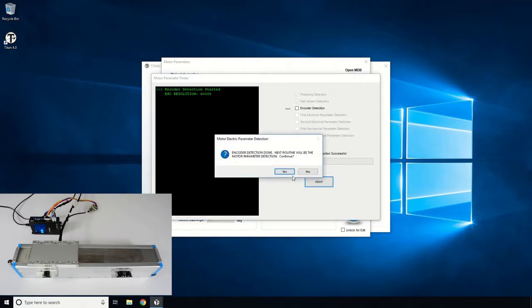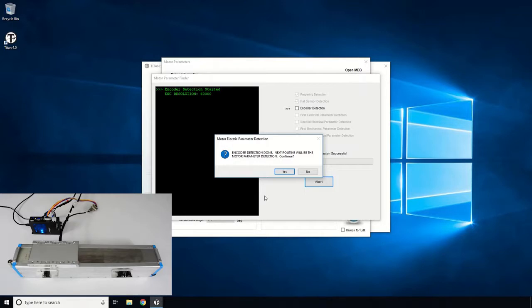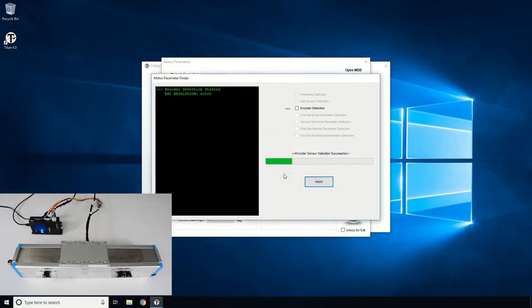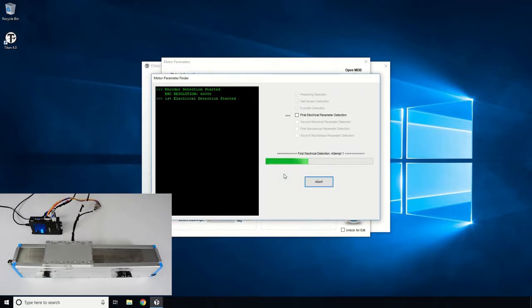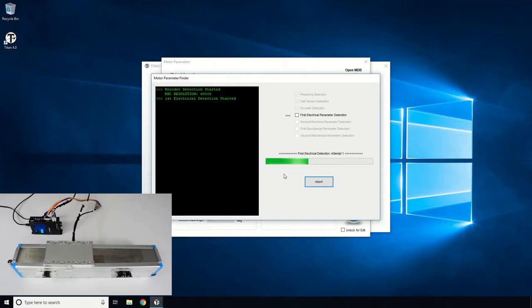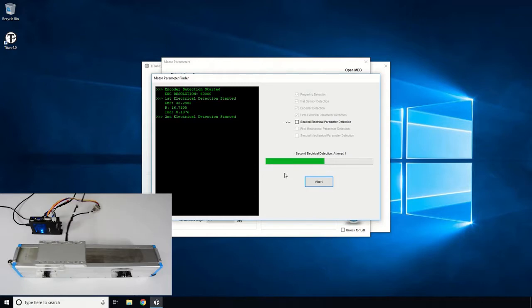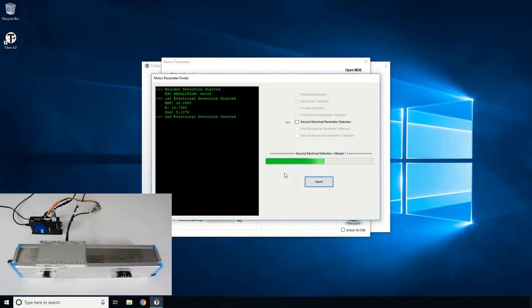Next, the electrical parameter values will be determined, such as the motor constant, resistance, and inductance values. Let's move the motor back manually to the midpoint and proceed with the electrical parameter detection. The electrical parameter detection sequence will run twice, once with a low strength and another one with a higher strength.